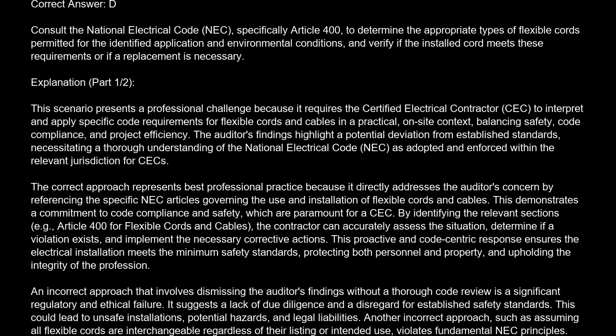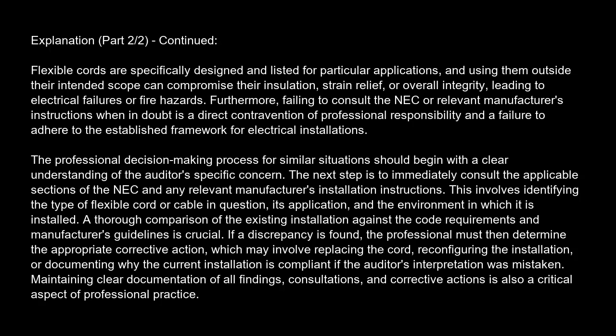Another incorrect approach, such as assuming all flexible cords are interchangeable regardless of their listing or intended use, violates fundamental NEC principles. Flexible cords are specifically designed and listed for particular applications, and using them outside their intended scope can compromise their insulation, strain relief, or overall integrity, leading to electrical failures or fire hazards. Furthermore, failing to consult the NEC or relevant manufacturer's instructions when in doubt is a direct contravention of professional responsibility and a failure to adhere to the established framework for electrical installations.